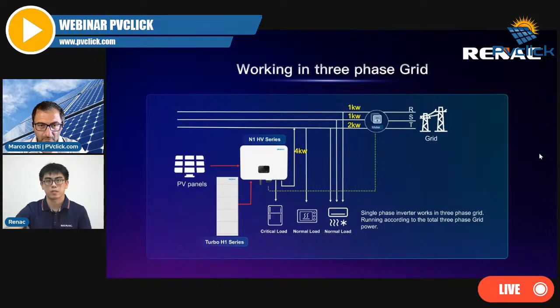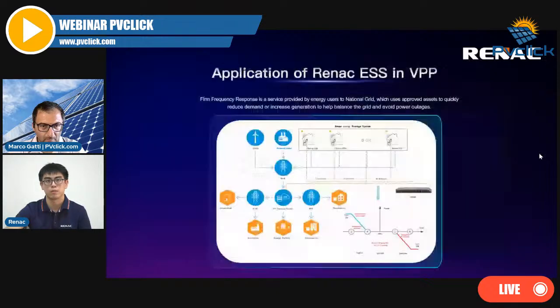This system also has the ability to work in three-phase grid, just using a three-phase meter to replace the original single-phase meter. Then the system can run according to the total three-phase grid power. For example, if there is 1 kilowatt load on phase R, 1 kilowatt load on phase S, and 2 kilowatt load on phase T, inverter will output 4 kilowatt power to balance the total three-phase power.